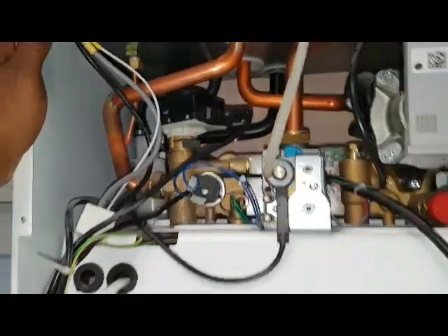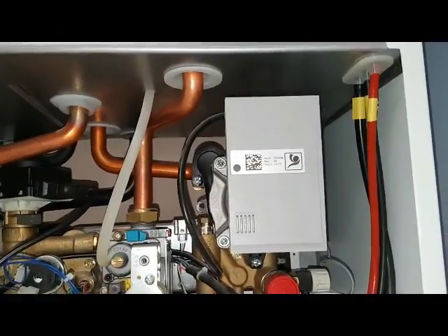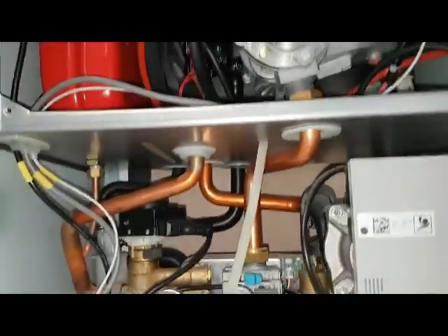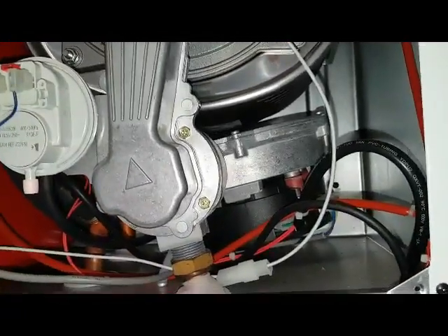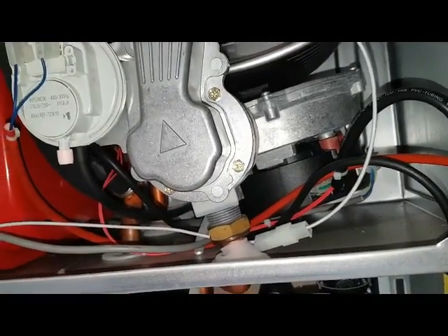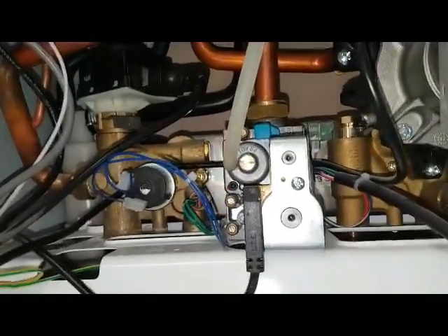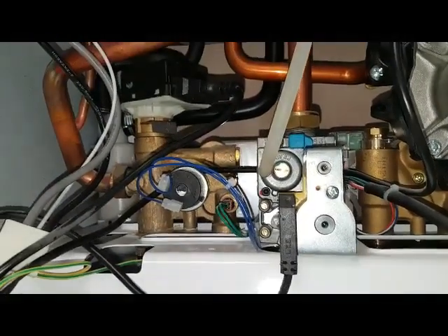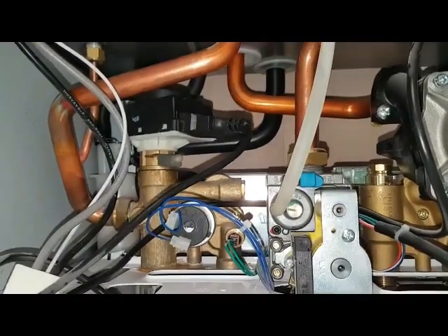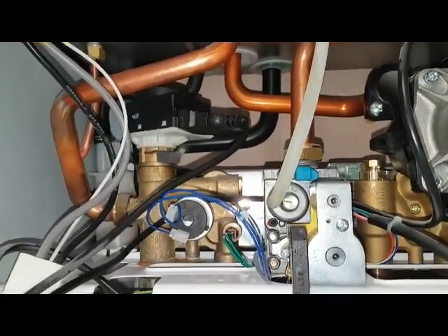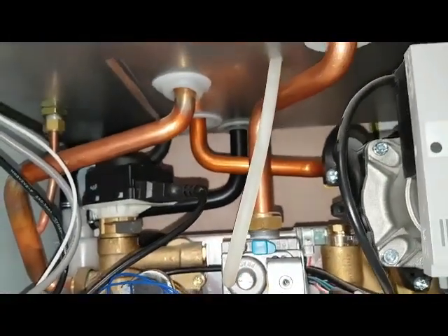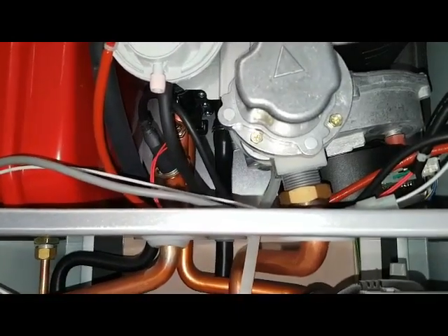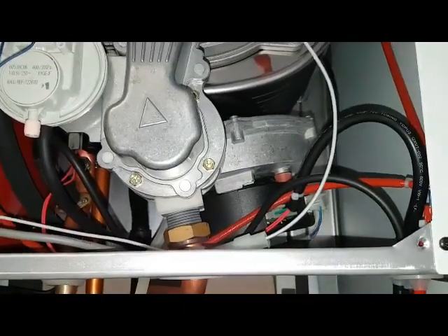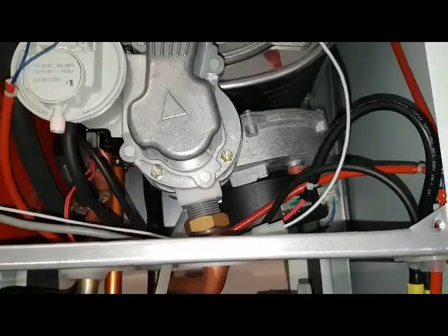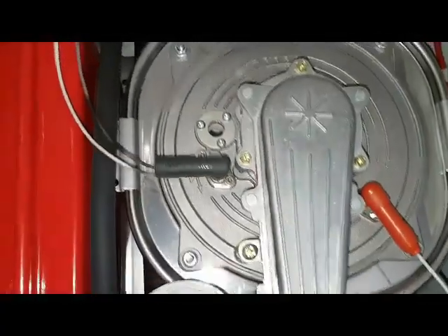So then, when that does that, the pump's running, okay? Then the fan here will start, that will turn. What'll happen then? The gas valve will open. The zero governor will basically have negative pressure put on it through that tube, what's generated from the fan. Then the gas is sucked up that pipe into the fan, mixed with air. So you've got an air and gas mixture. Goes up this mixing tube and burns.